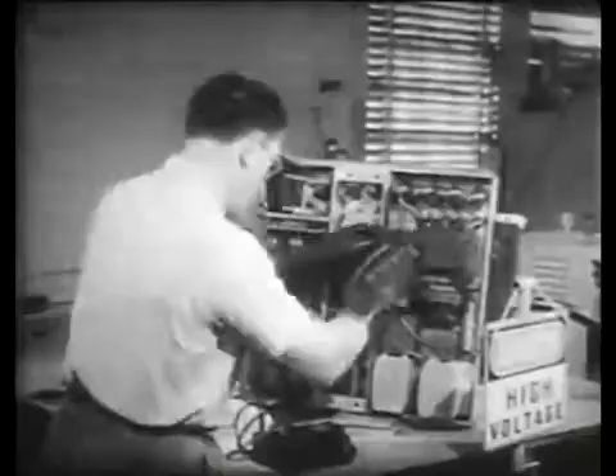Here's the proper routine. Make a habit of this procedure and you won't get hurt. First, de-energize the equipment. Cut off the power. Then discharge the capacitors and touch the grounding bar to the terminals which are to be used in the test.